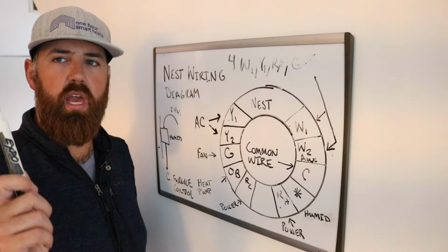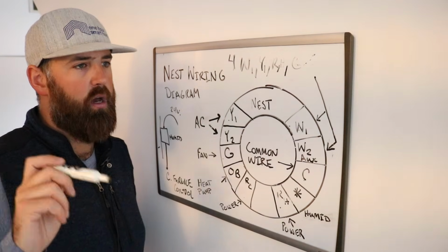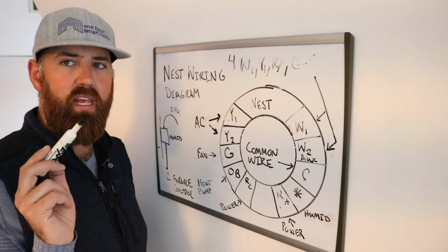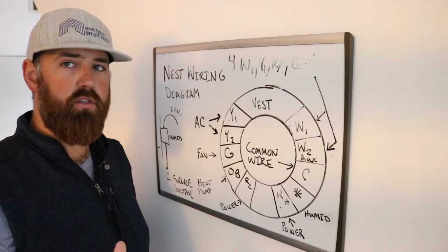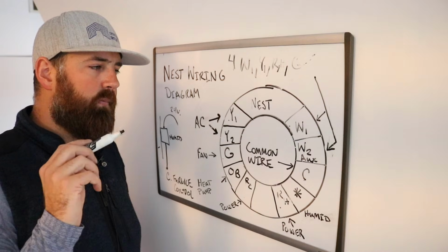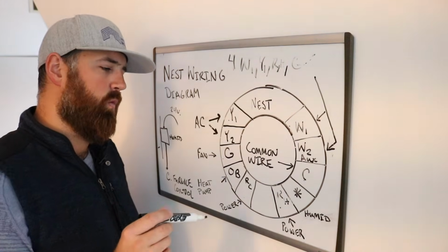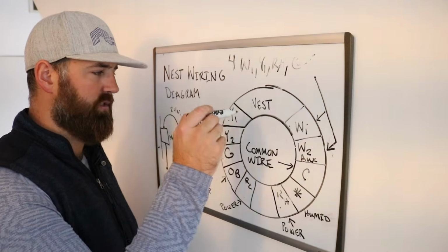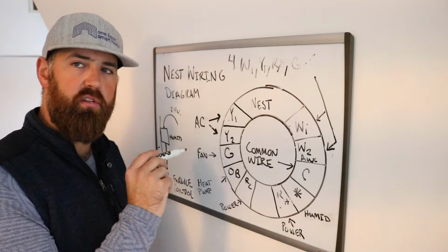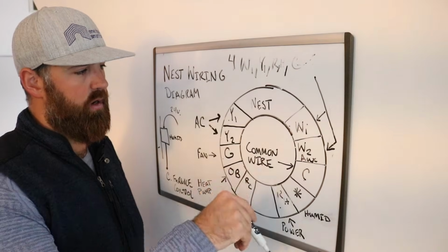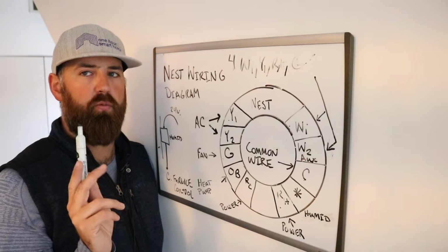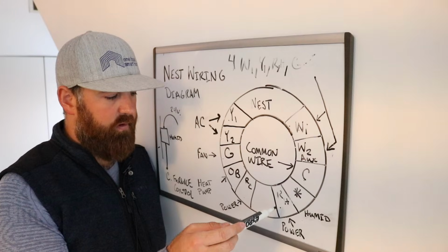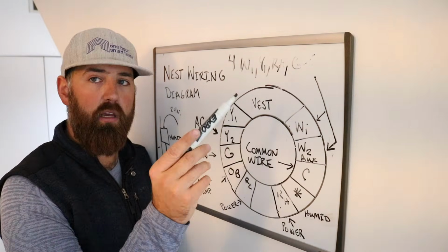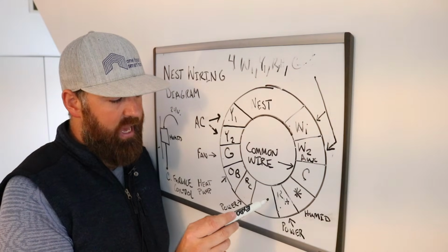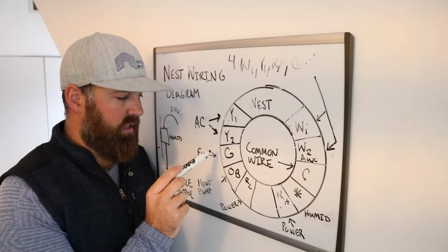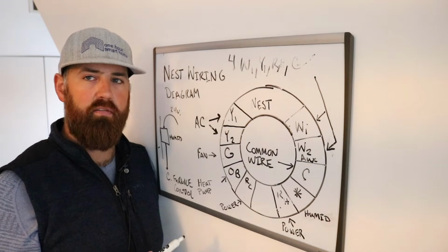The other case is when people only have heat, no air conditioning. If you live in a northern climate where it's not too humid and you get moderate temperatures, you may only have a heat furnace. In that case you may have 2 wires or 3, because in modern furnaces the blower motor automatically turns on whenever there's a call for heating or cooling, so you don't necessarily need the G wire—you'd just lose the ability to blow air around without the heat on. For a 2-wire system you'd have RH and W1 for heating from your furnace. Or with 3 wires, you'd have RH, W1, and G, so you can still circulate air without having the heat on.